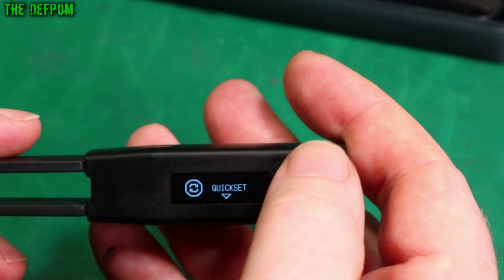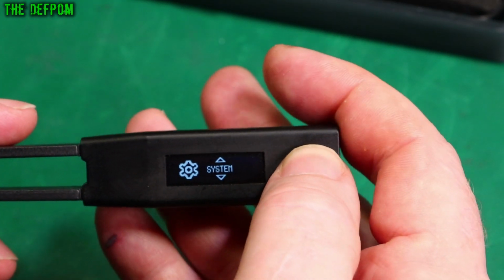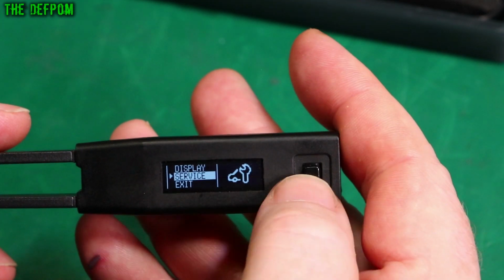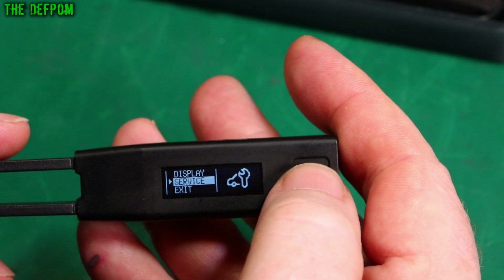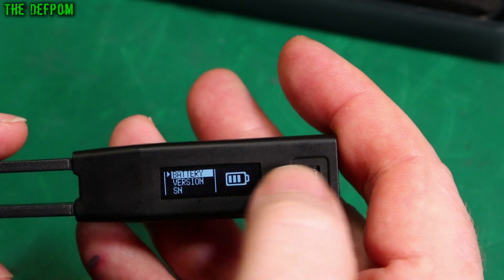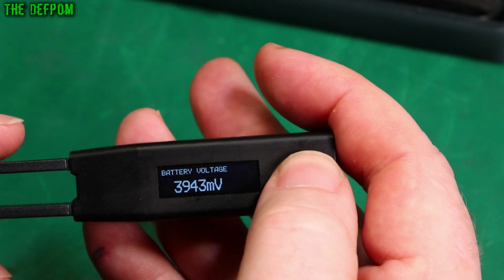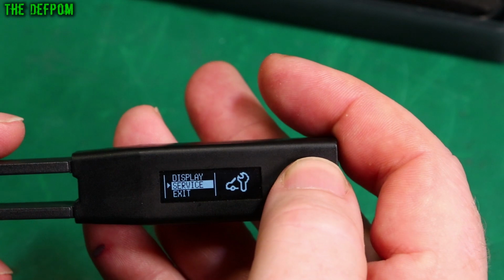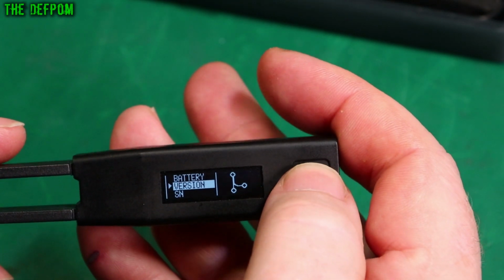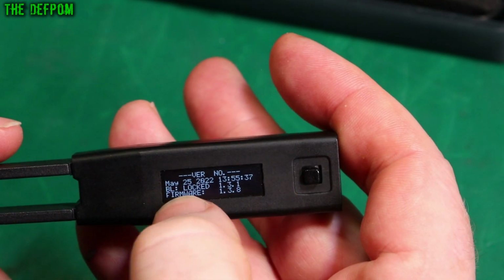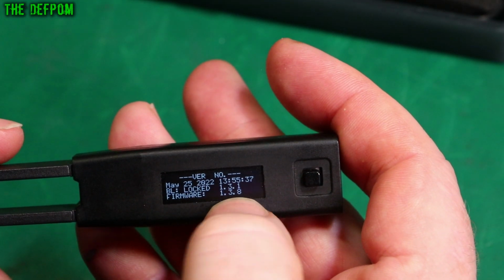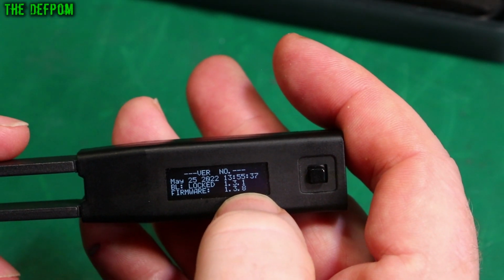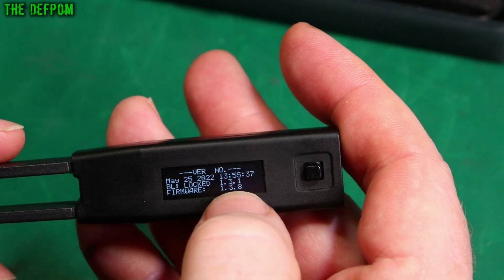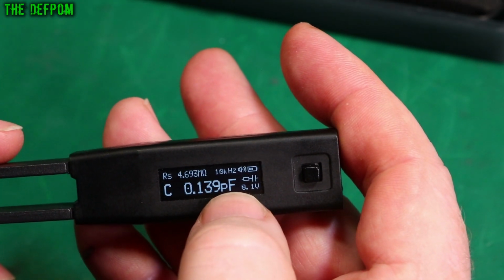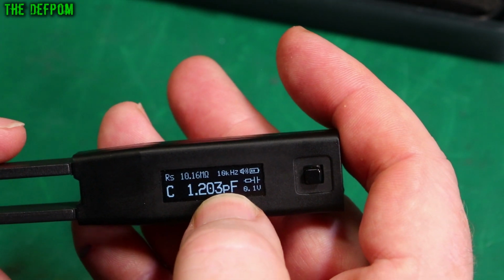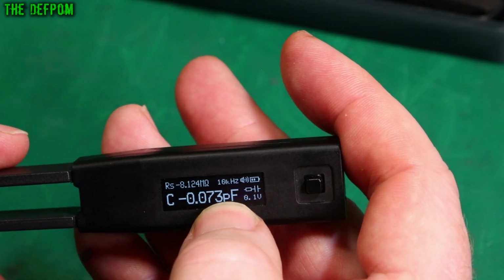So something I should show you in the system menu. I'll go back in. So system menu, service, that's further down, right? So you've got the display which you showed before, service. You go in here, it tells you information about the battery, so it tells you the battery voltage. System, service, version. So it tells you information about the actual unit. So it's got firmware information, things like that. So this is using 1.3.8 right now, and that's an older version of the firmware. So this obviously is current when it was sent to me, but there's now a newer version which is 1.4.2.